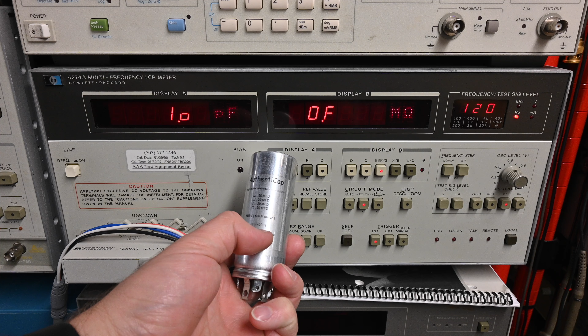The new capacitor showed up today. I figured I'd show you guys how it tests on the LCR meter, since I'm not sure anyone's shared the test results of one of these Authenticaps. This is Authenticap, made by F&T Cap in Germany. It's rated 550 volts continuous and 600 volts surge, and it's got 4 sections: a 30 microfarad section and then 3 20 microfarad sections. Let's first hook it up to the half moon, which is the 30 microfarad section.